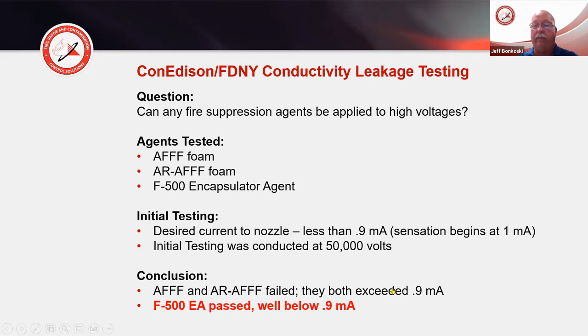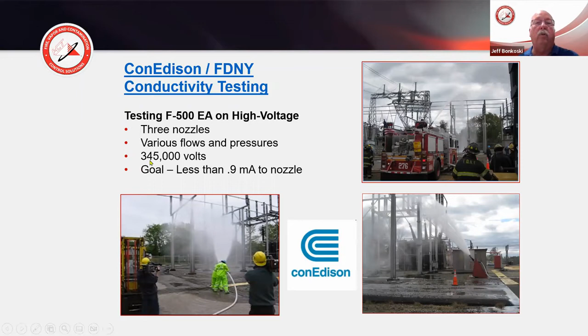F500 passed. And they did it with different nozzles and different patterns. They used 3 nozzles and different flows, and the goal was to have less than a 0.9 milliamp current feedback. And these are the results. When they used a fog nozzle at a 30-degree fog pattern at a distance of 25 feet, the current was at 0.9 milliamps. That was the limit. When they went to the deck gun, it was 125 feet that they needed to be away for it to be less than 0.9.